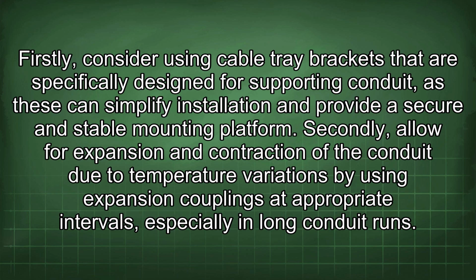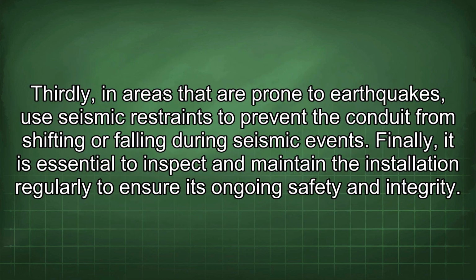Firstly, consider using cable tray brackets that are specifically designed for supporting conduit, as these can simplify installation and provide a secure and stable mounting platform. Secondly, allow for expansion and contraction of the conduit due to temperature variations by using expansion couplings at appropriate intervals, especially in long conduit runs. Thirdly, in areas that are prone to earthquakes, use seismic restraints to prevent the conduit from shifting or falling during seismic events.